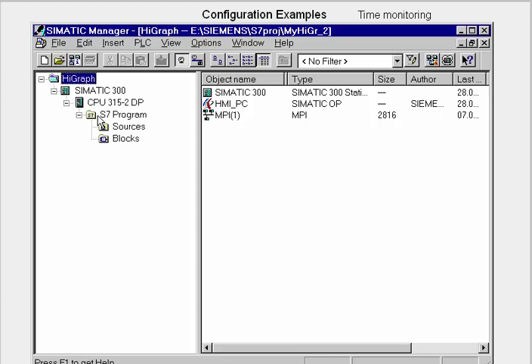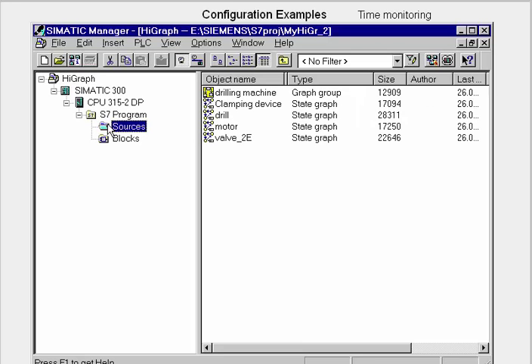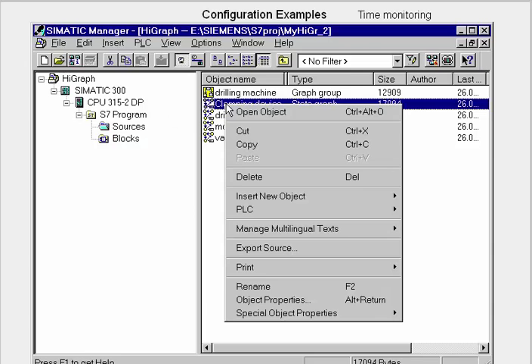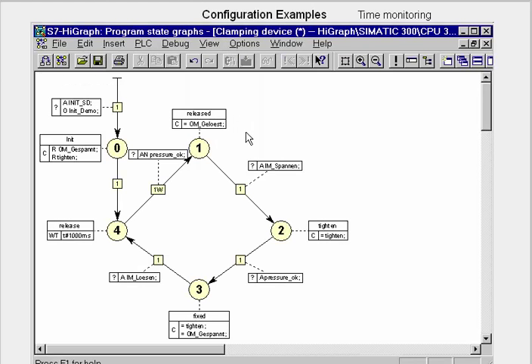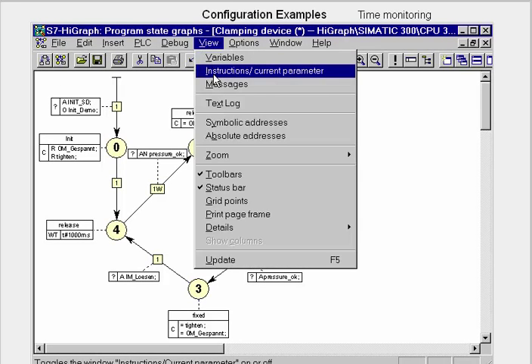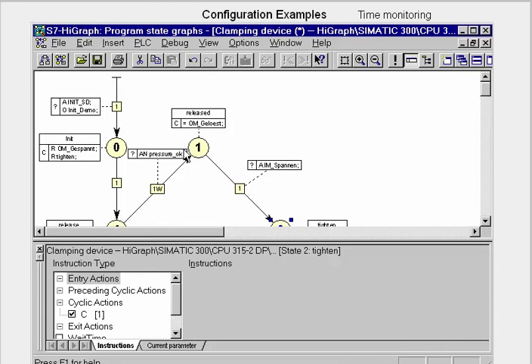The following example shows the configuration of simple state monitoring in the S7 HiGraph language. In the SIMATIC Manager, we open the relevant state graph entitled Clamping Device. Here, we want to time monitor state 2. For this, we only have to parameterize a maximum state dwell time with a monitoring time.